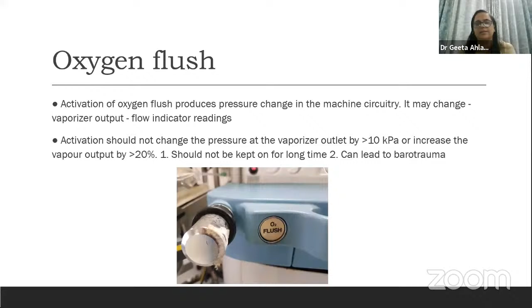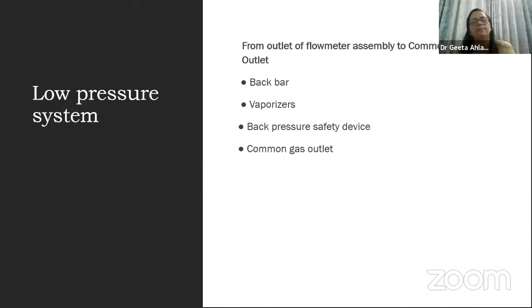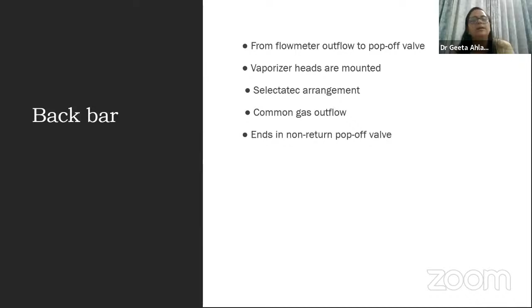Now coming to the low pressure system, from the outlet of the flow meter to the common gas outlet. All of us are aware it houses the back bar, vaporizers, back pressure safety devices, and the common gas outlet. Nowadays it is not visible, but you can see it very clearly in the Boyle's machine. There was a pop-off valve which would pop off in case there is any kink or any back pressure, so that the patient is saved and it does not cross to the common gas outlet. Vaporizer heads are mounted on it. It makes place for the Selectatec arrangement and leads to the common gas outlet.